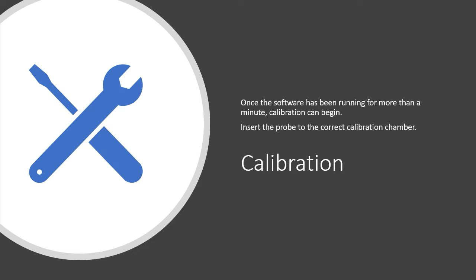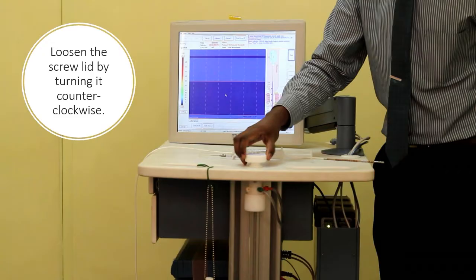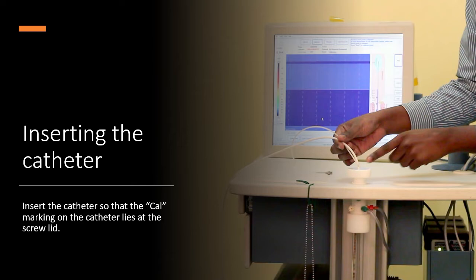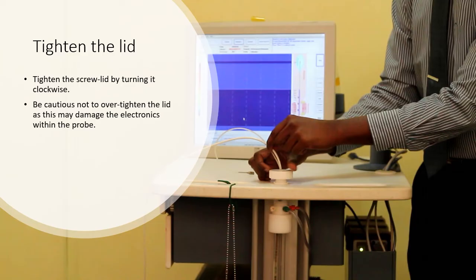Before patient measurements can begin, the probe must be calibrated. Once the software has been running for more than a minute, calibration can begin. To insert the probe into the calibration chamber, first loosen the screw lid by turning it counterclockwise. Insert the catheter into the calibration chamber until the marking indicated as Cal lies at the level of the screw lid. To tighten the lid, turn it clockwise. Be cautious not to over-tighten the lid, as this may damage the electronics within the probe.